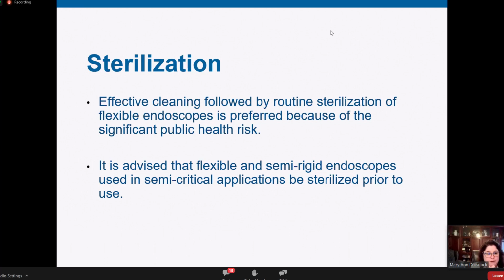But as a group, we felt, as Garland said earlier, that we do need to move to sterilization over the next few years because there is this higher risk associated with endoscopes and high-level disinfection. So although sterilization is not foolproof, it still requires complete and effective cleaning. We still have to completely dry that scope before sterilization. We still need to do our inspection and cleaning verification, but we just have that higher margin of safety. So we do recommend sterilization for all scopes, but as Garland said, we can't always get there.